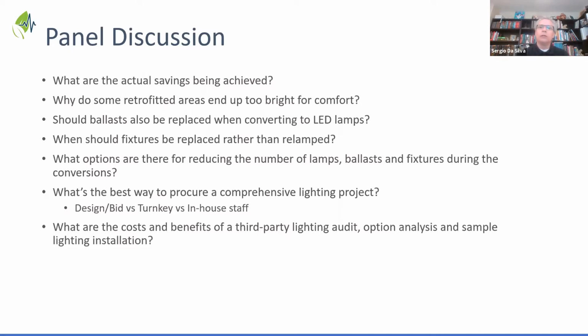So we recommend replacing ballasts that are over 5 years old, outside of their warranty period. But first and foremost, we recommend an initial assessment of what's on site, some samples to verify that what's on site will accommodate a various assortment of lamps, 2 foot, 3 foot, 4 foot U lamps. You run the risk of some manufacturers' products working well on one ballast and not necessarily on another. But for the most part, any of the newer products being introduced into the marketplace will certainly work on the bulk of newer electronic ballasts.